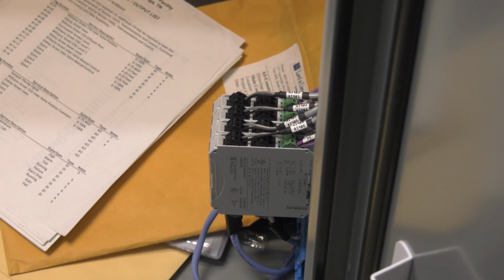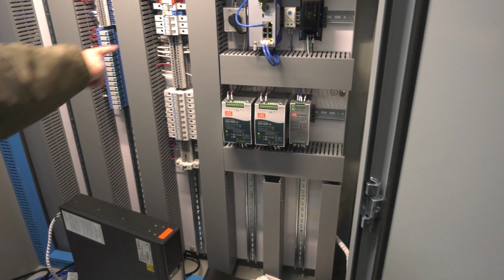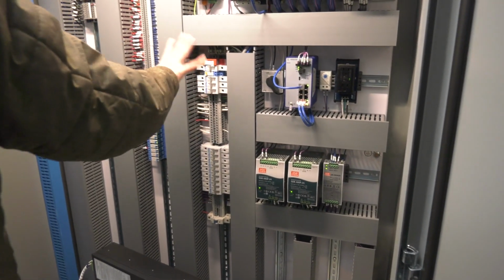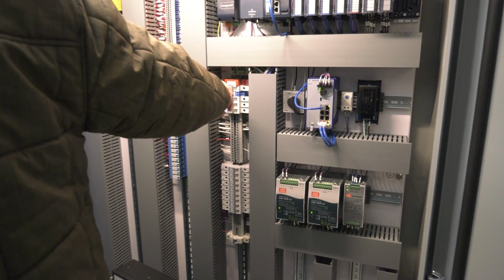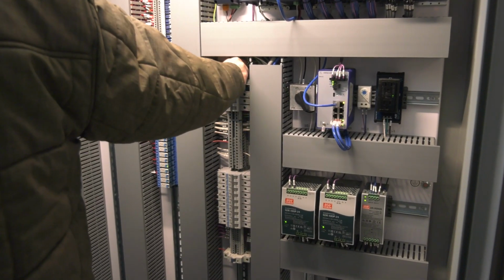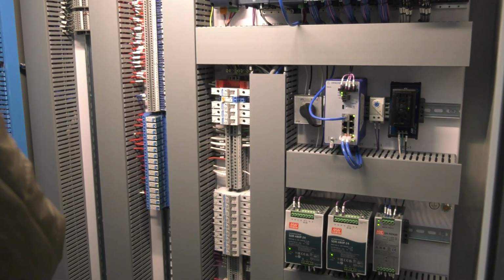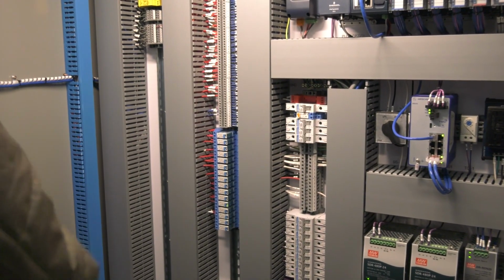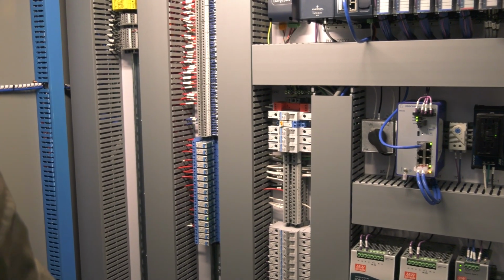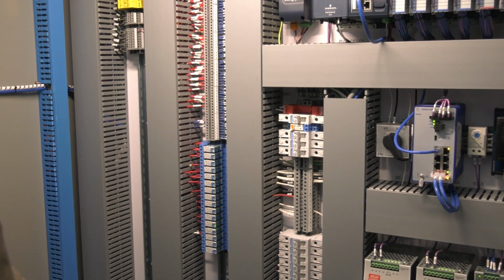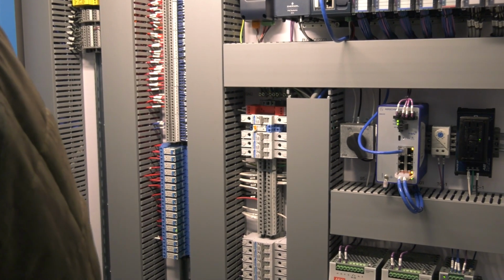And I don't see much need in cycling this again. But you got your UPS and bypass. And this is your main breaker right here. So if you have to kill power for any reason, just flip that. And again, this right here, make before break. This is your 120 volt surge suppressor. If you lose this, just pull this out, and when you get a new one, replace it.